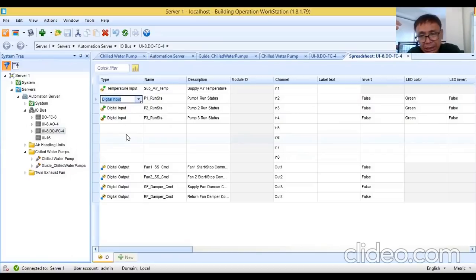It will be an auxiliary contact from the contactor or main contactor of the pump, okay? So since this is connected to a VFD, even if the pump is big, there will be no star-delta connection. It will be direct online through the VFD, okay? So from the motor control, there will be a contactor there, okay? Now, from the auxiliary contact of the contactor, I will be getting one normally open contact for the use of run status, okay? So how am I going to create it?